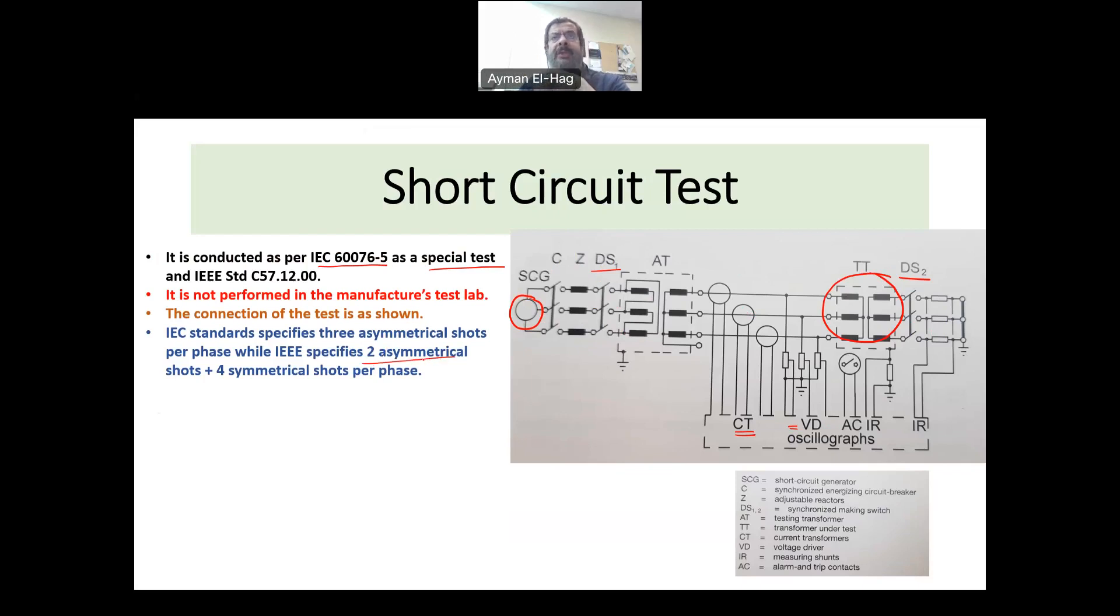The last question is, how do I know if my transformer passed the test or failed the test? First of all, you have to do all the routine tests before you start the test. Why? To compare them after you do the test. Because if there is any failure in the transformer, there will be some deformation. And this deformation will impact the dielectric strength and the impedance of the transformer. So you will measure those quantities after the test.